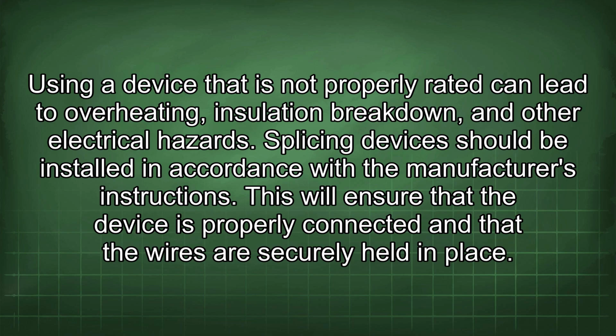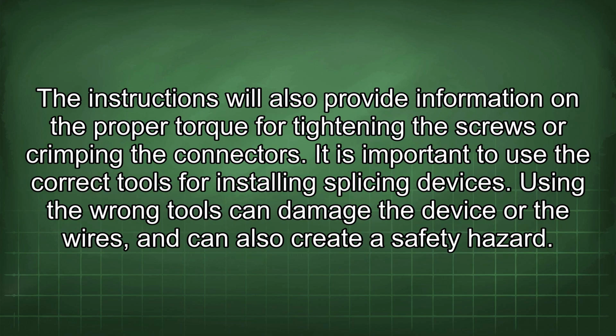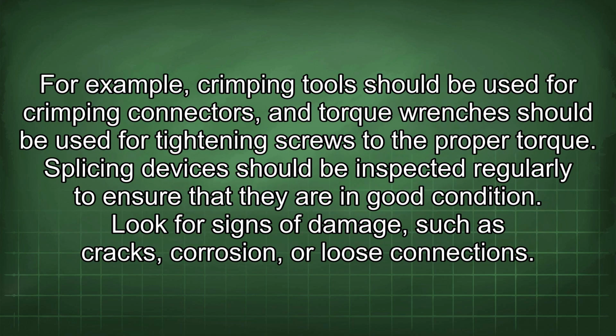Splicing devices should be installed in accordance with the manufacturer's instructions. This will ensure that the device is properly connected and that the wires are securely held in place. The instructions will also provide information on the proper torque for tightening the screws or crimping the connectors. It is important to use the correct tools for installing splicing devices. Using the wrong tools can damage the device or the wires, and can also create a safety hazard.